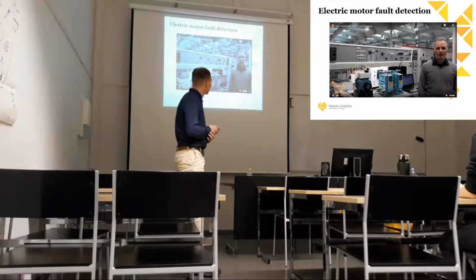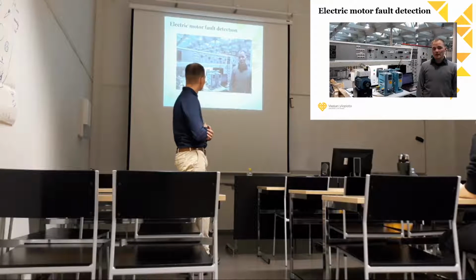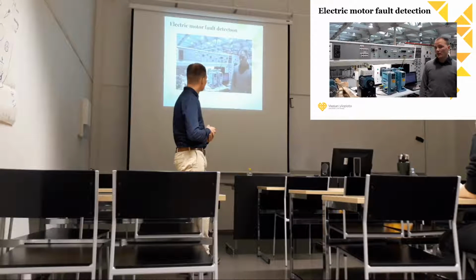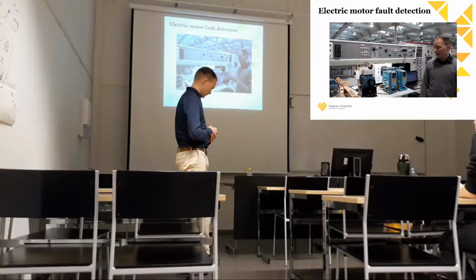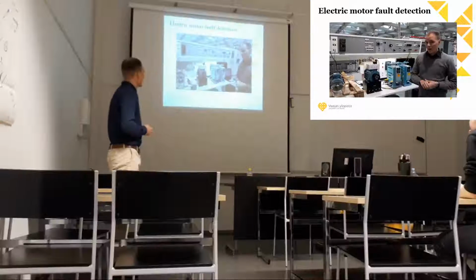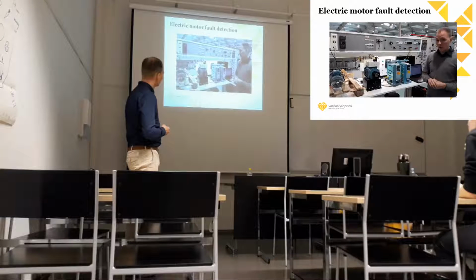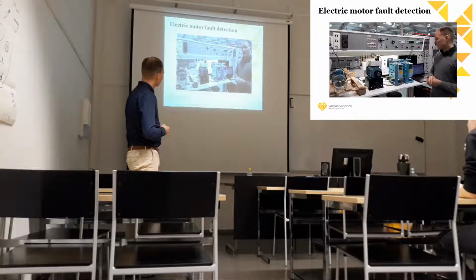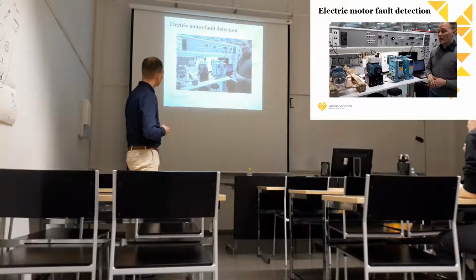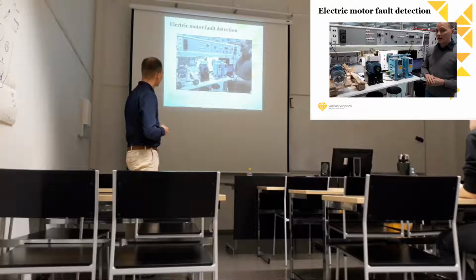Hello, I'm Thomas. We are here at Technobotnia. Today we are testing out fault detection of electric motors based on sound. And we have a test setting here that we have two motors here. One of them is has a bearing fault and another one is normal. So let's start first by listening to the voice of the motor, and let's see if we can recognize which one is the faulty motor and which one is the normal motor.